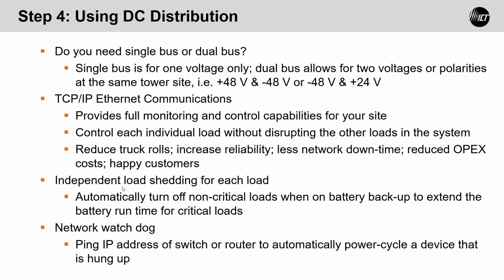We also have features such as independent load shedding for each load, which means that each load has an LVD capability, a low voltage disconnect. So you can automatically turn off non-critical loads when on battery backup to extend the runtime for critical loads. So if you've got a device like a camera or something that is not critical to the site, you could set the load shedding voltage higher on that device. So when you were running on battery, when it reached that voltage, it would shut that device off and give you more energy from your battery to be able to run the critical loads longer.